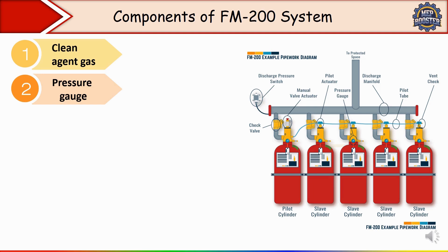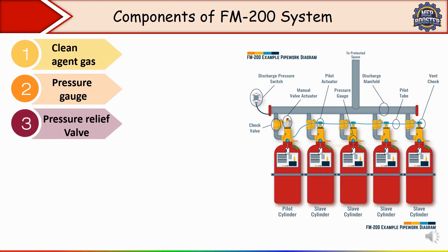The second component is the pressure gauge — a mechanical gauge that attaches to each FM-200 storage cylinder, displaying the pressure inside to help monitor whether the cylinder is fully charged and ready for activation. Regular pressure checks ensure the system is operational. Next is the pressure relief valve — a safety valve installed in the system to release excess pressure. Then there is the pilot line — a pneumatic or hydraulic line connecting the primary cylinder to secondary cylinders in a multi-cylinder system. When the primary cylinder is activated, the pilot line opens the other cylinders, ensuring simultaneous discharge of FM-200 gas.